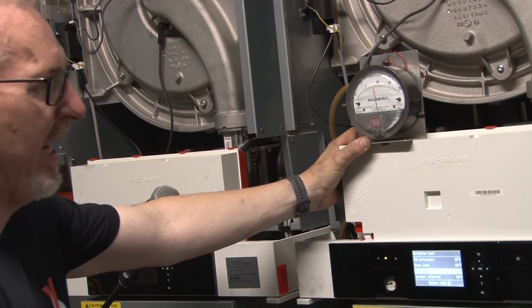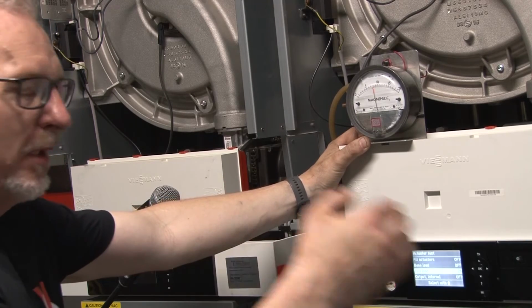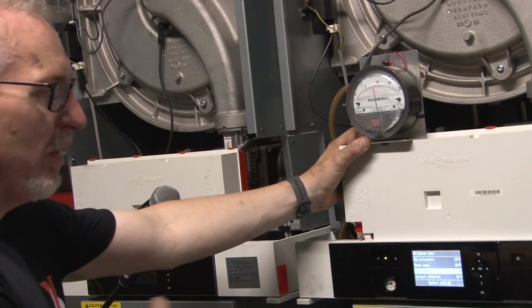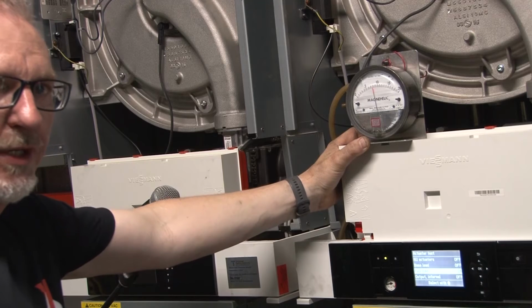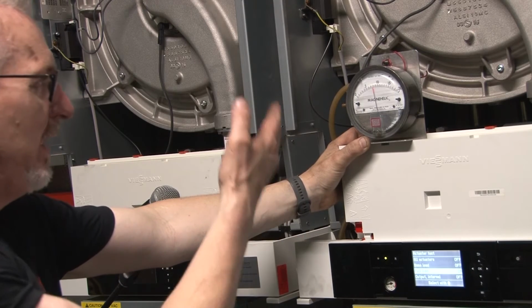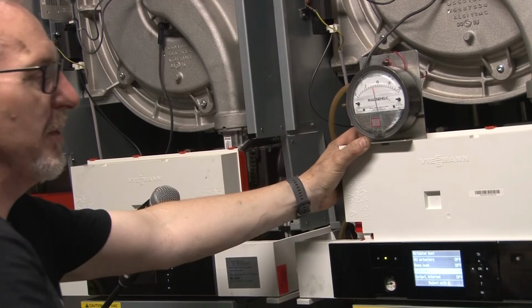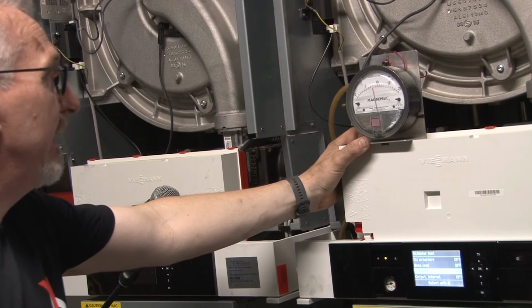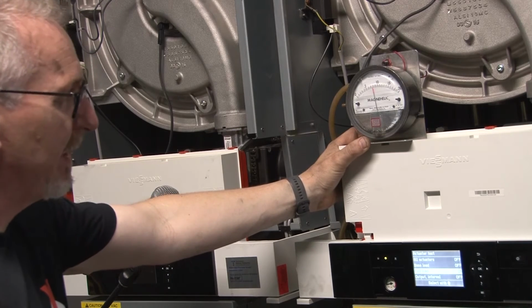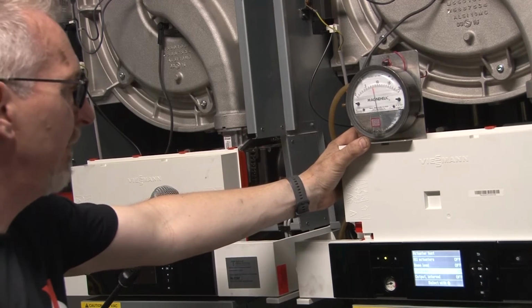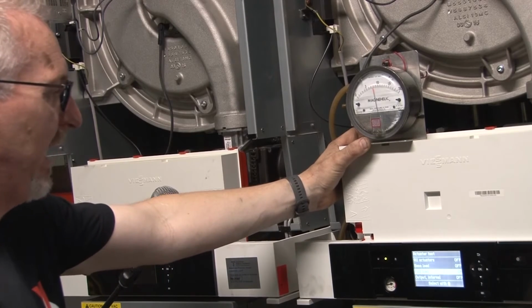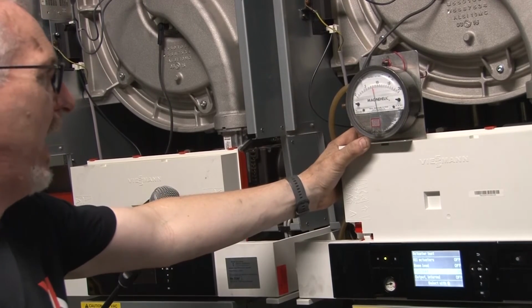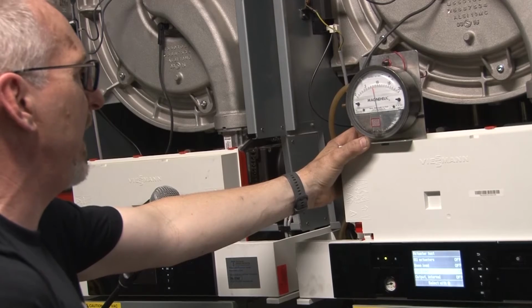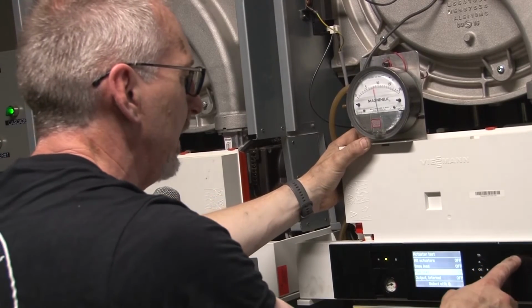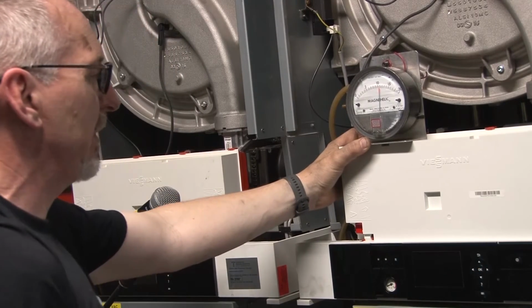calibration. What they have here, they only have one gas reg on these boilers. You would really want to fire all your boilers on high fire because you want to see, with all those boilers on full load, where does that gas pressure end up? It's nice when they're individual regs because now you basically test these boilers. So there we go, high fire, that's stable at high fire, and we dropped to about 8 inches. So the last check is what we do is lockup pressure.